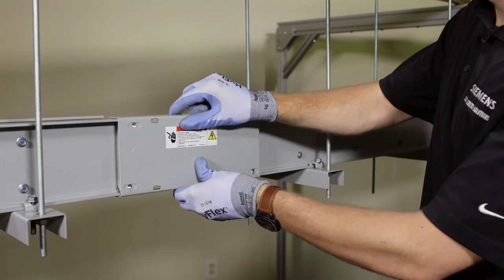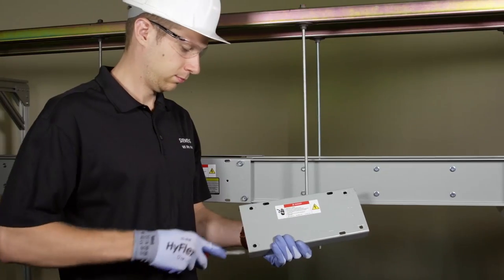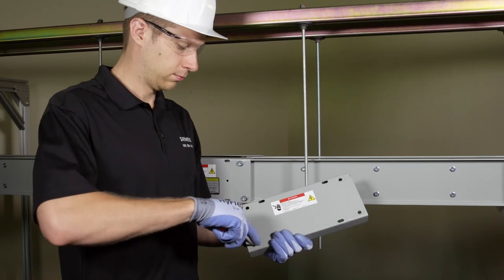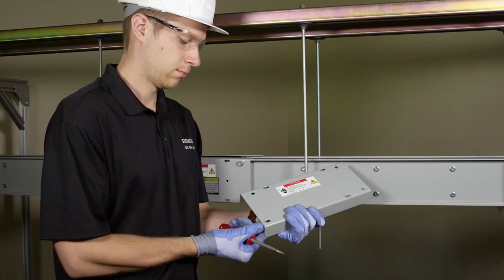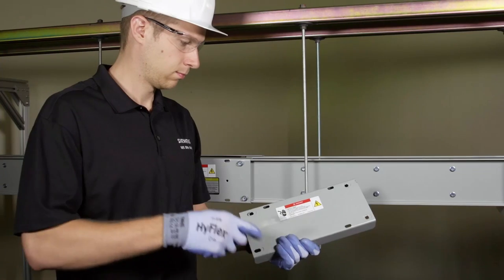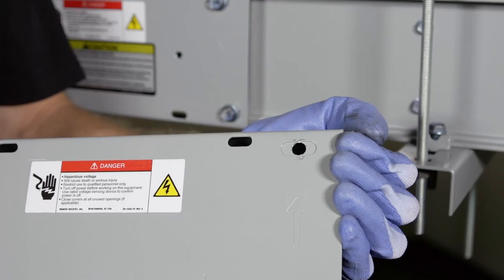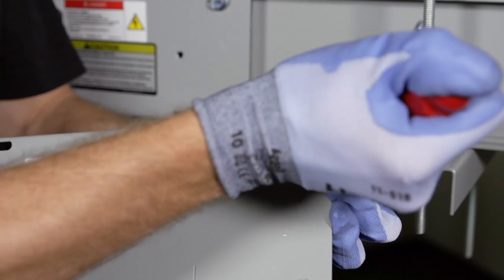Loosely fasten the remaining joint cover to the busway to confirm the joint is aligned properly. The mounting holes in the joint cover should line up with the threaded holes in the joint supports. Sentron busway joints are adjustable to plus or minus 5/8 of an inch or 16 millimeters. The standard distance between the two joint supports is 8.25 inches or 210 millimeters. If you need to make adjustments, remove the appropriate knockout tabs in each joint cover.